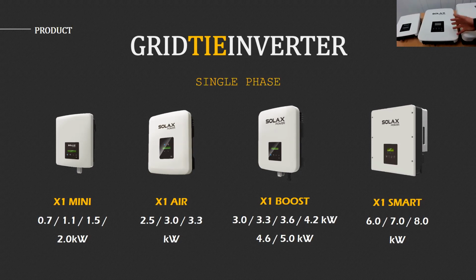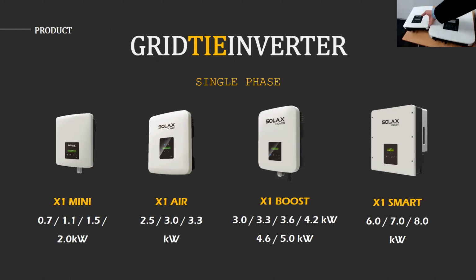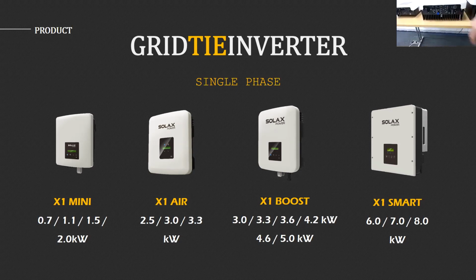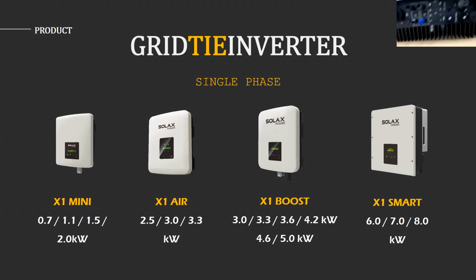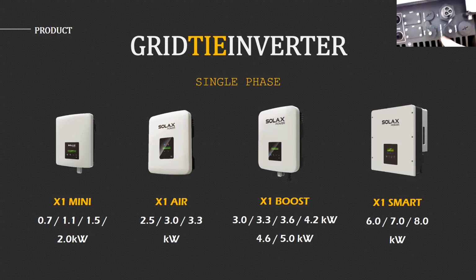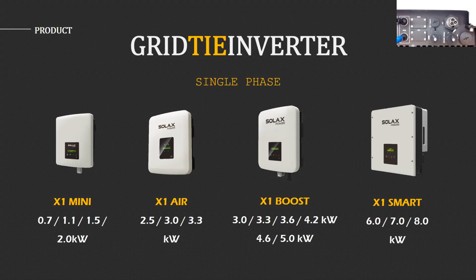As you can see, it's a little bit bigger than the other one. It's a single phase inverter with 2 MPP trackers and a single phase output. Let me go a little closer. Here you can connect the meter, so we can realize with our PV inverters a dynamic reduction or power limit, or a static power limit. That means if you have some demand in your house, the power wouldn't be limited to 70% as long as you can use this energy yourself.